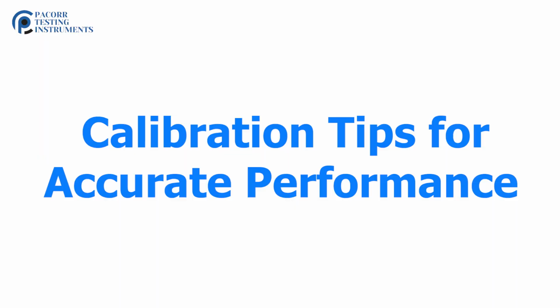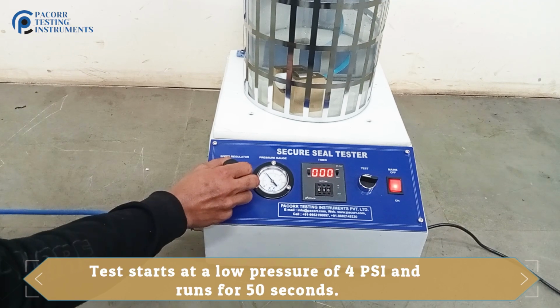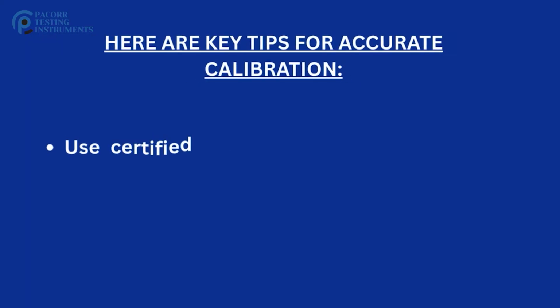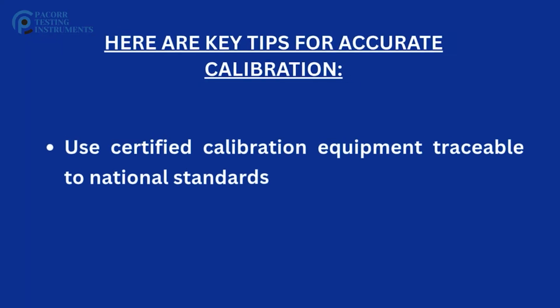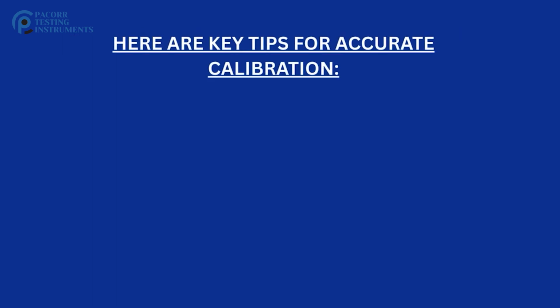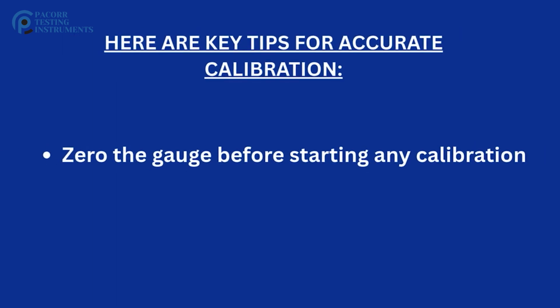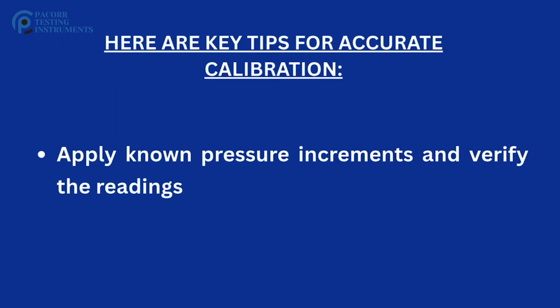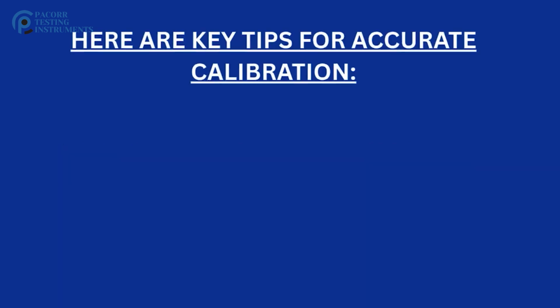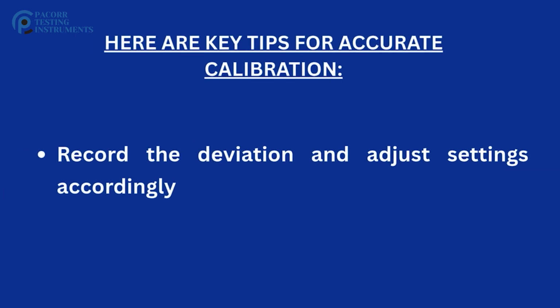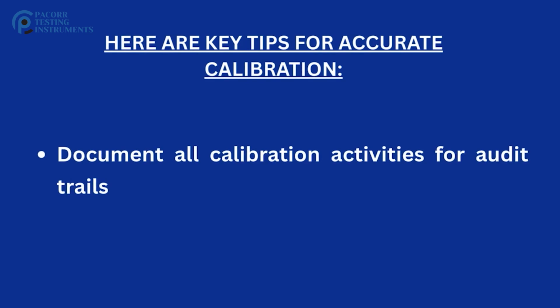Calibration tips for accurate performance. Here are key tips for accurate calibration. Use certified calibration equipment traceable to national standards. Zero the gauge before starting any calibration. Apply known pressure increments and verify the readings. Record the deviation and adjust settings accordingly. Document all calibration activities for audit trails.